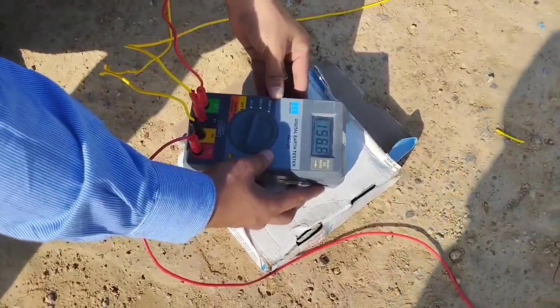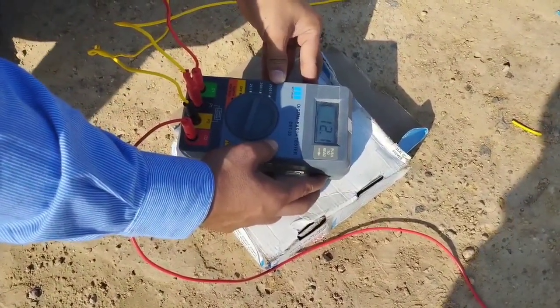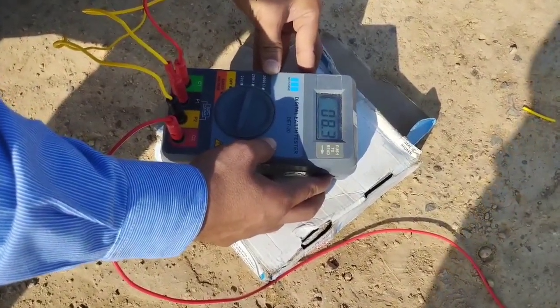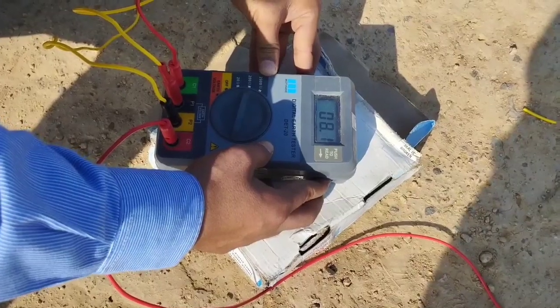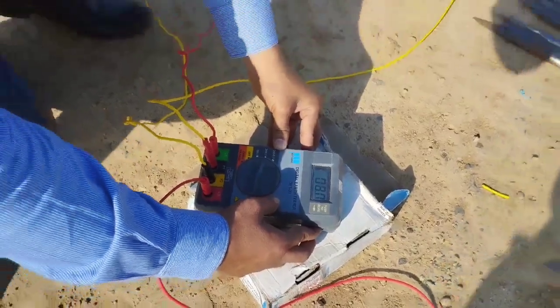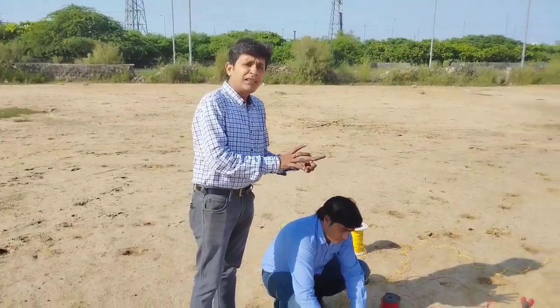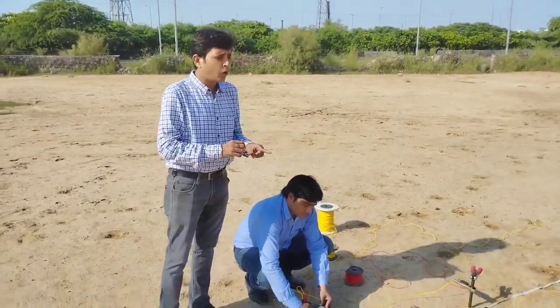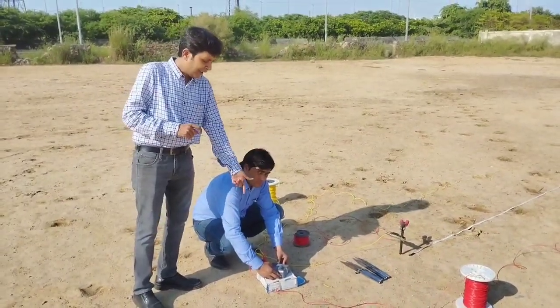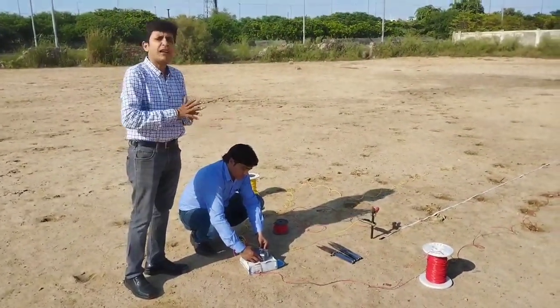At the same range of 200 ohm, we will get the reading. Earlier it was 8.4, in the range of 8.3 to 8.4. It has reduced because this time the voltage drop due to shorting of C1 and P1 in the earth tester has been compensated. This is the actual value.